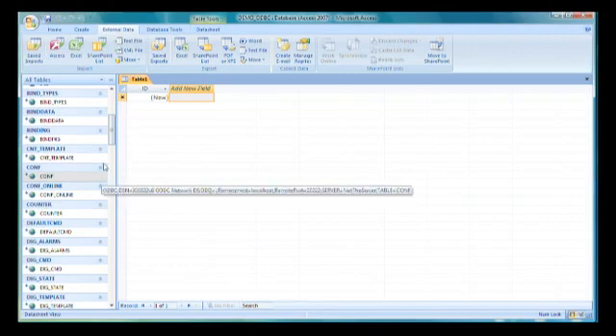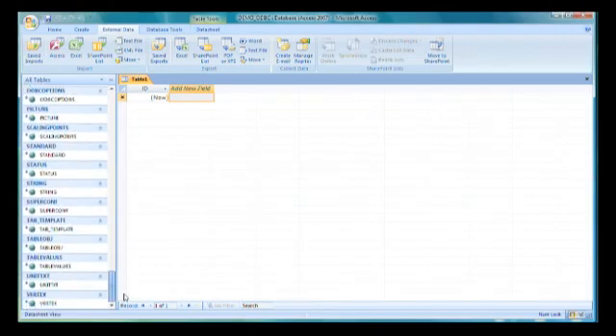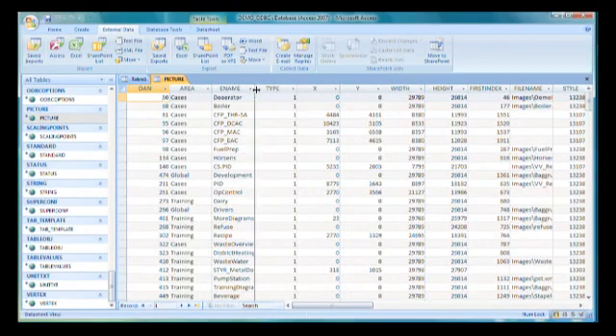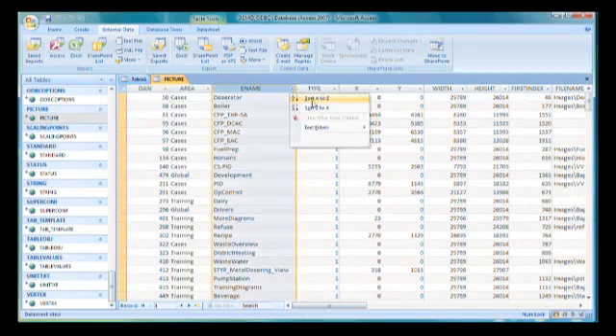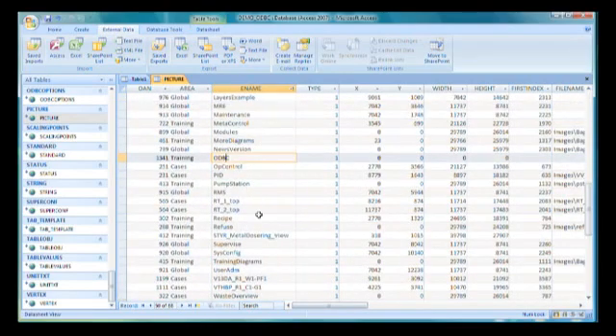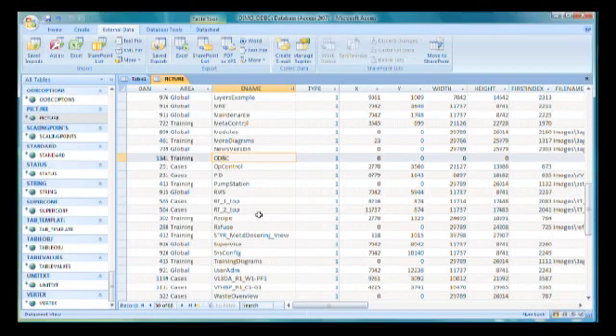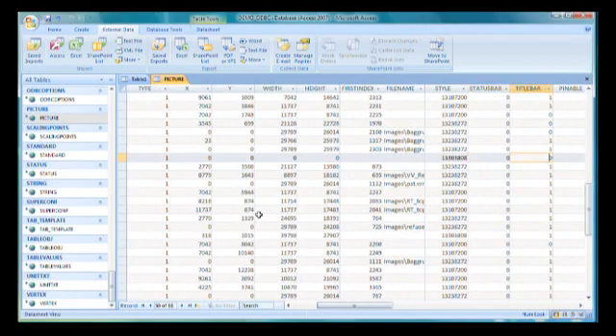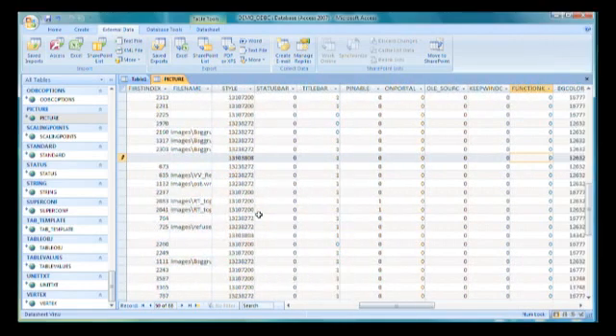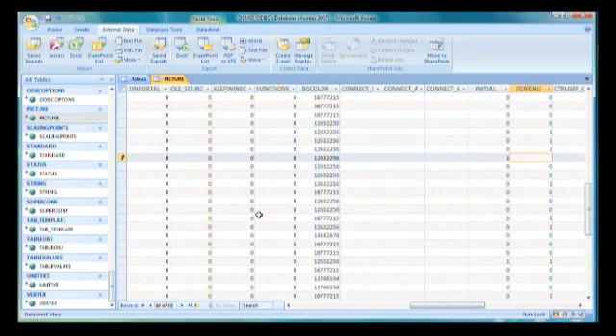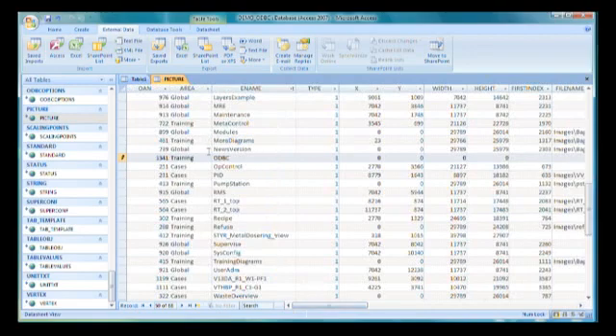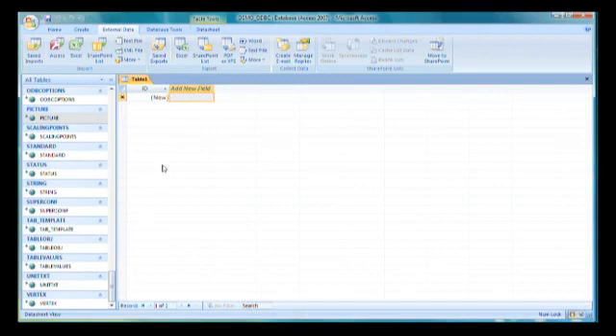When we create this diagram in the conf table, there will also be a record in the picture table. The picture table is where we have all the diagram properties. If we sort on ename, we can find our ODBC diagram. Here it is, ID 1341. This is a diagram where we want the title bar to appear. We want it to be the initial window, the first one that appears when we start up. All these properties we can now set directly in this database table. When I close this, I have actually defined an entire diagram.